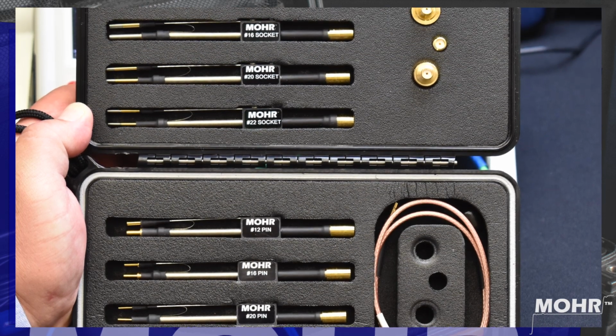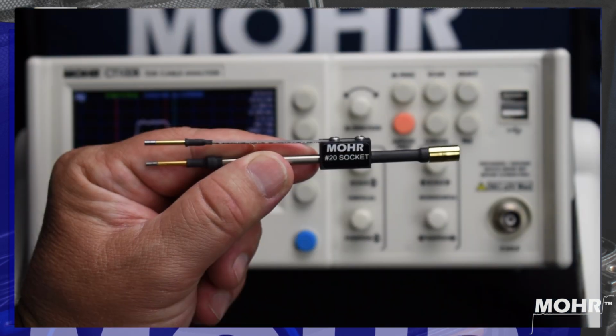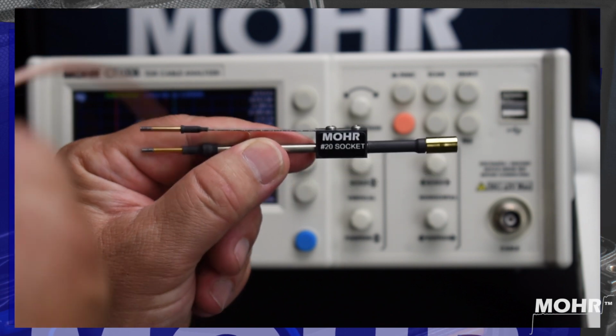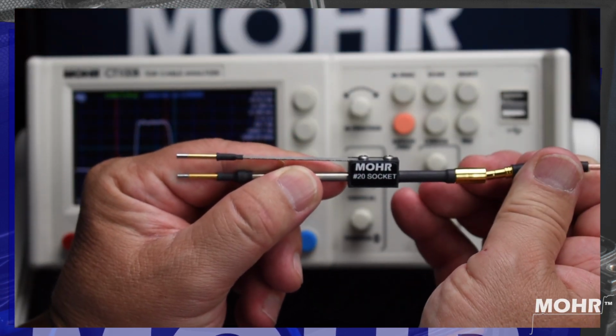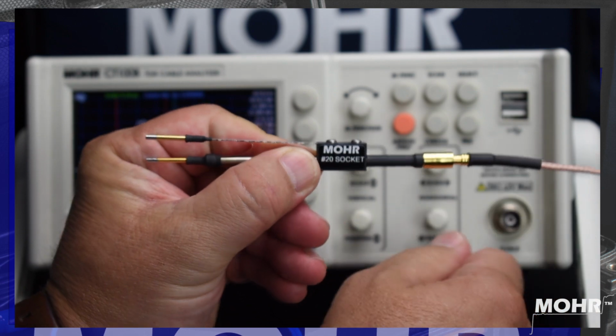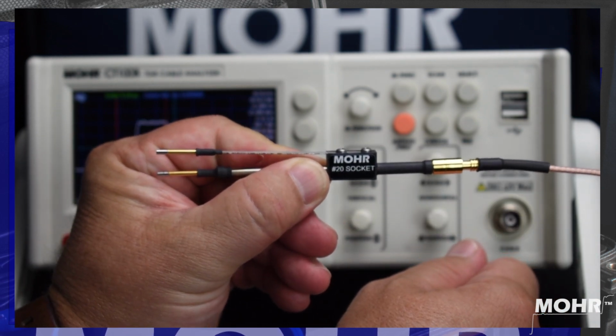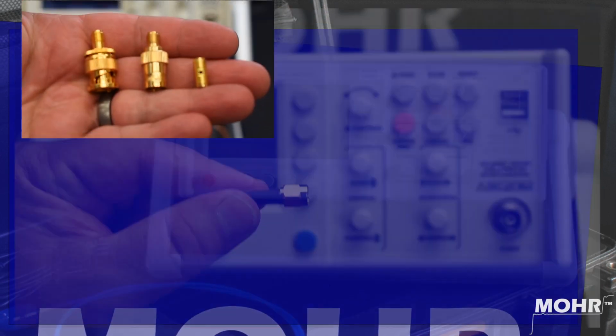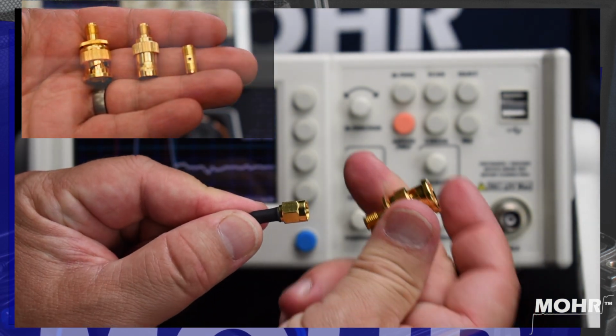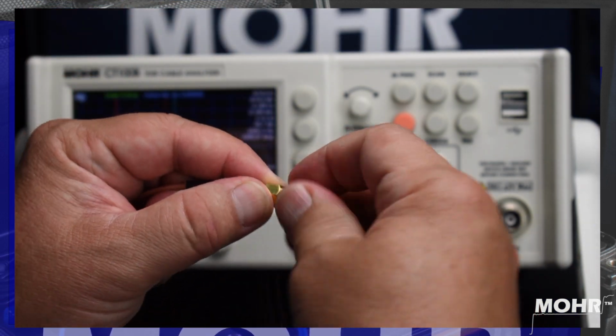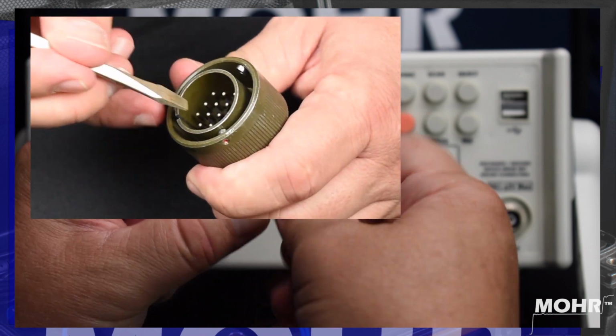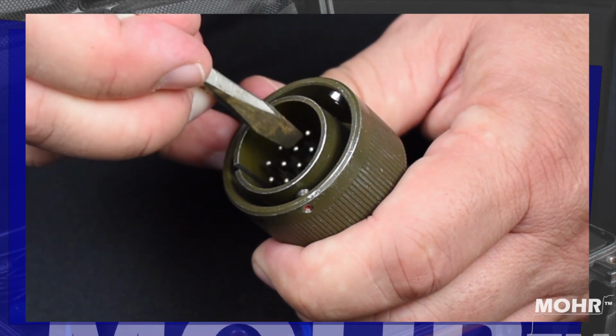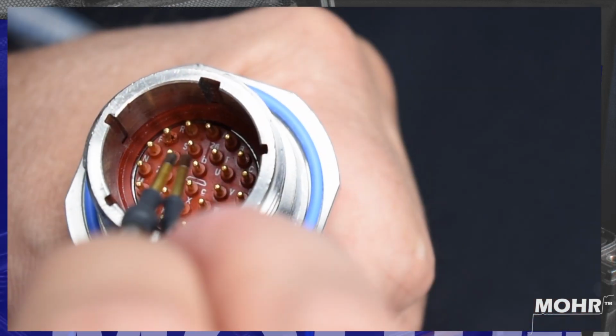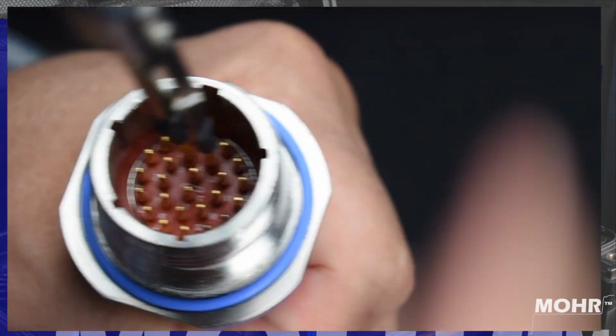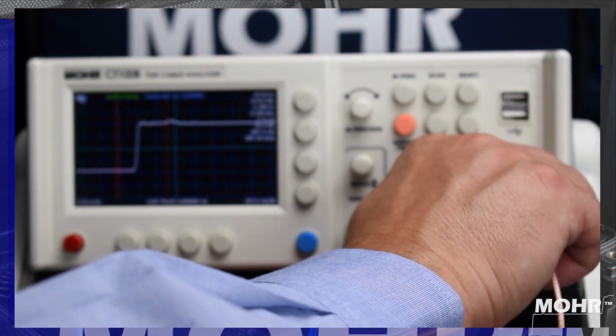To use the pin and socket set, select the size of pin or socket probe that will be needed. Today we're going to use the number 20 socket probe. Connect the cable provided to the probe. Connect the cable to the desired BNC adapter. After verifying power has been disconnected and everything's powered down, short pins to discharge the static. Connect the probe to the desired pins, then connect to the CT100B.